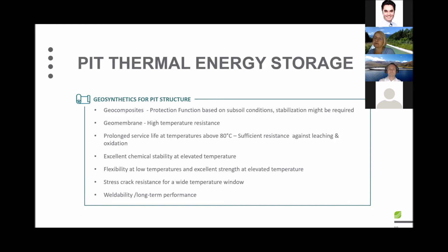And it has to offer prolonged service life at temperatures above 80 degrees. We are talking about 90 degrees in a lot of applications, and 95 degrees is also to be considered. So it needs to offer sufficient resistance against leaching and against oxidation in this case. It also has to provide excellent chemical stability at such elevated temperatures, because there are chemicals used for the water which is stored in it.